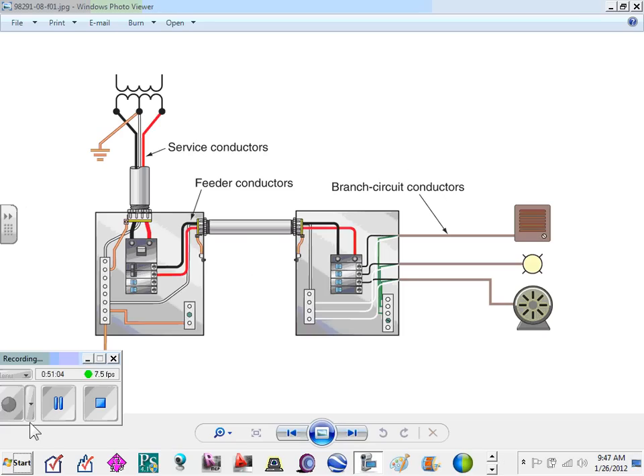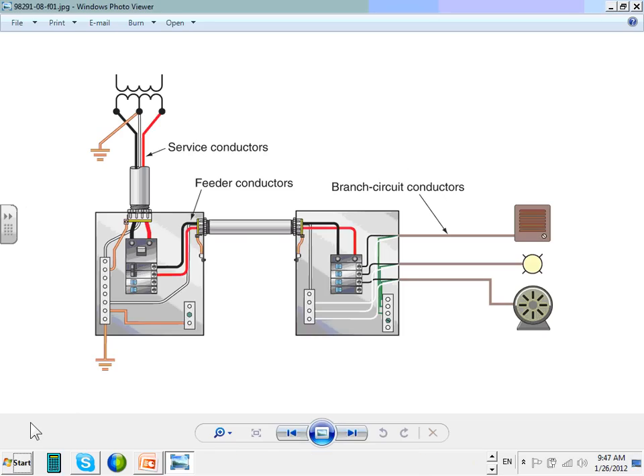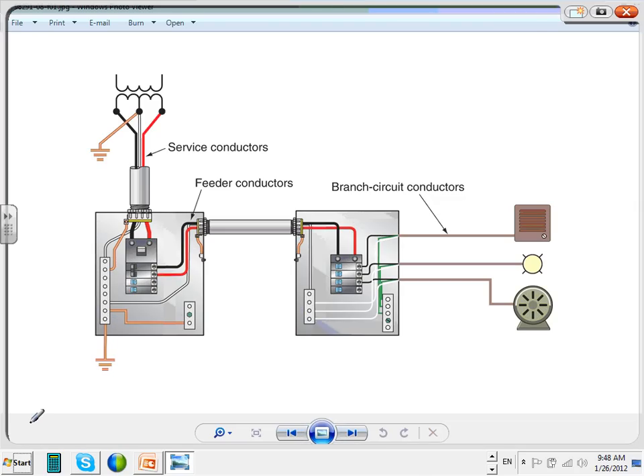So a couple of things, guys, if you don't know by now, please do. When we have any power system, you're going to have utility coming in. The first thing you're going to have is the service. This is covered by NEC Article 230. The NEC code book has a complete article that covers the conductor coming from the utility transformer into your building. You guys have sized multiple of them now. You sized 2 systems for Chad.